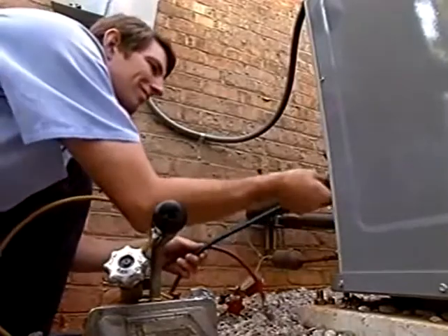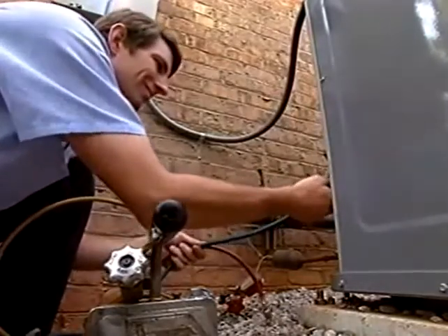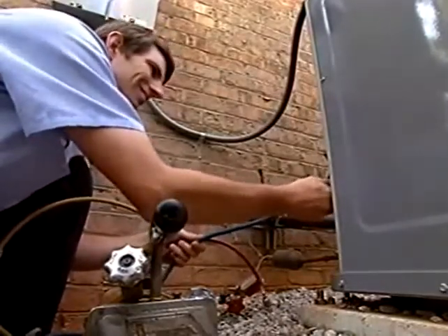Actually, bigger is worse. Oversized units can cause a number of comfort and service problems. What happens when we oversize our equipment is that we have shorter run times and what we call short cycling. And in our heat pumps and our air conditioners, the system basically gets its maximum efficiency after it has run for a certain amount of time. Depending on the piece of equipment, that could be 10 or 15 minutes before it gets to its steady state of operation.